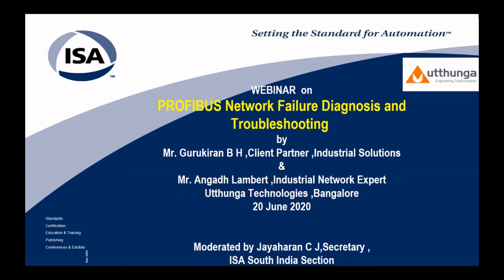Before we start with PROFIBUS, what it is all about: it's basic digital communication between your sensors, PLCs and SCADA systems. Digital communication is becoming very popular nowadays, out of the bus architecture. PROFIBUS is basically a standard 485, we call it the RS-485 bus. It's an enhanced version of the RS-485 bus, a multi-drop environment, and there are very specific cabling requirements and impedance requirements to be followed. Those are the pros of PROFIBUS. As for the cons, the speed reduces over the length. So as and when you have a longer PROFIBUS network, you really have to compromise on the speed.